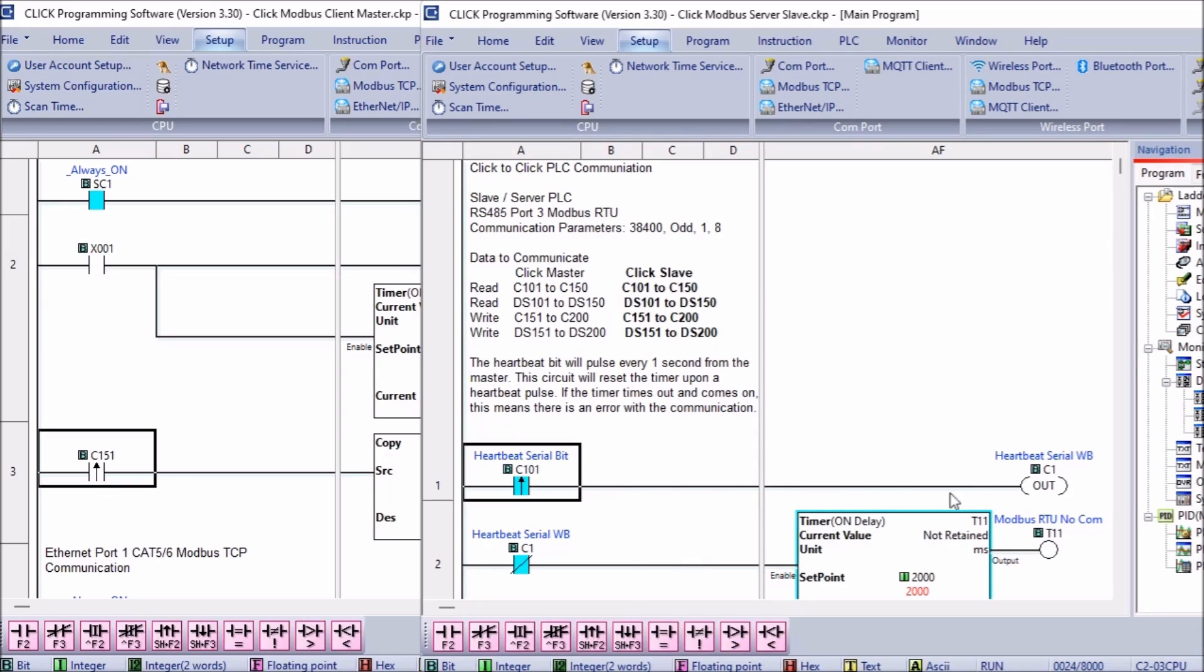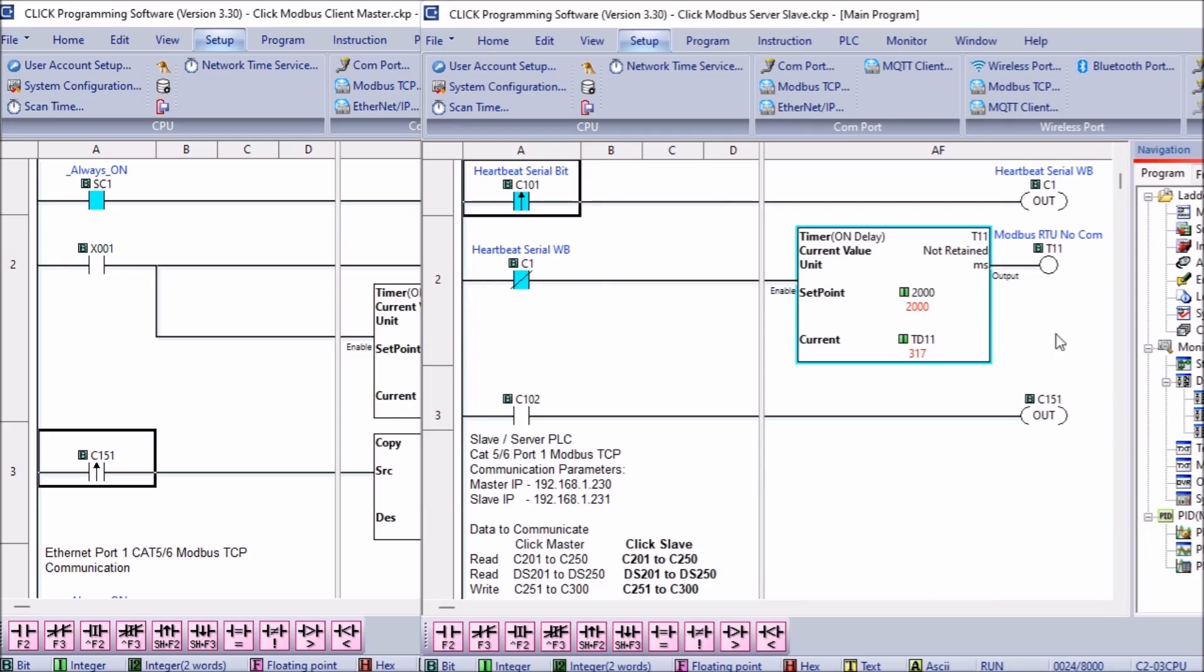Using the leading edge of this bit to turn on an internal bit we use this normally closed internal bit as the condition for the timer. If the timer times out and the timer done bit comes on we know communications has been lost.